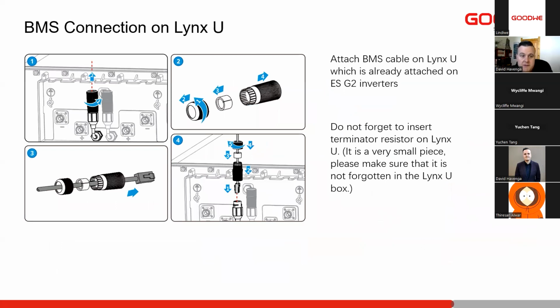The BMS communication to the inverter. As you'll see, we've got these nice little connectors. You simply unscrew it, remove the blank cap, push the cable through, clip it into the connector first, and then we can screw and close the connector. So always make sure you click the cable in first, so you hear the click and it is nicely secured. Then we can put the outside cover down and lock it to the cable to make sure it cannot be pulled out.